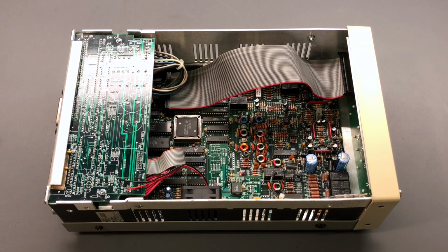So there's a ROM chip that's on the main circuit board. When the instrument is created or built at the factory, the calibration is set up and it's permanently coded into that ROM chip, all right, which is very handy because that ROM chip is always there. It doesn't require a battery or anything like that, and the data is always there. And that data is good as the instrument leaves the factory.